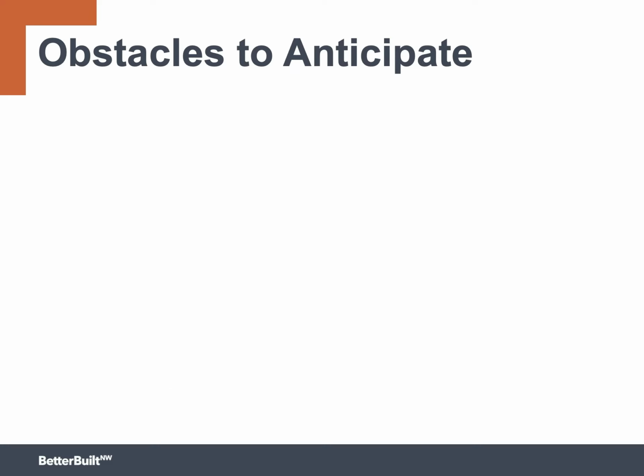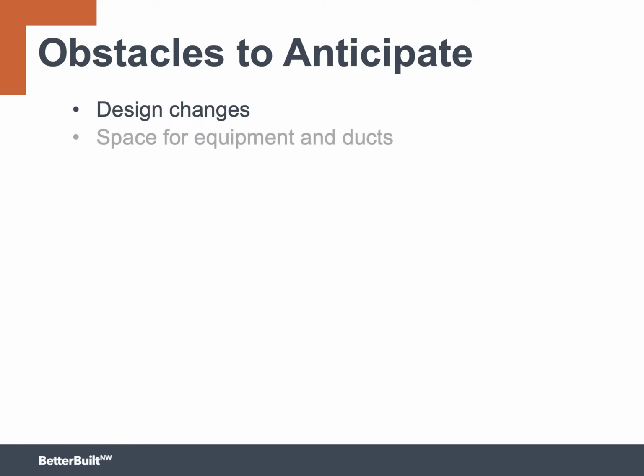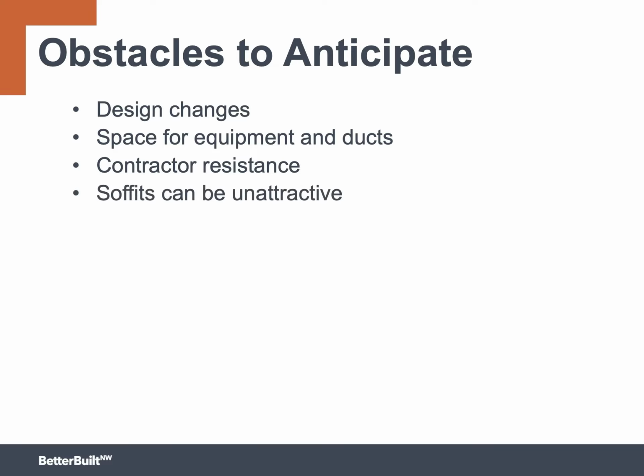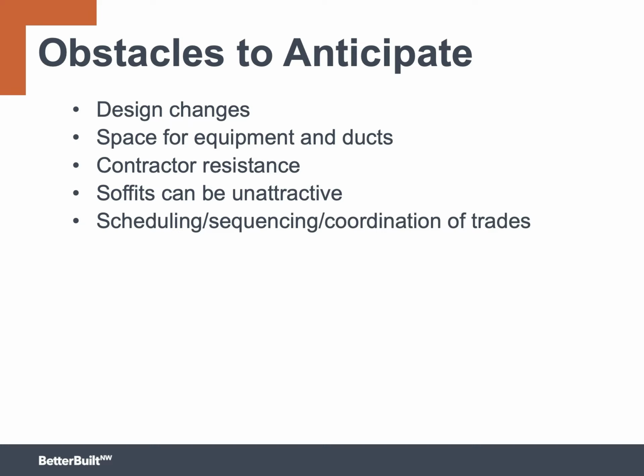There are some potential challenges to building with ducts inside too. You can have design changes such as the issue of extra height in the building. You can have challenges finding space for the equipment inside the conditioned envelope. You may find that the trades are resistant to this whole idea and you have to overcome some pushback. Some people may view soffits as unattractive. Sometimes scheduling or sequencing of the trades can be an issue. You might lose some interior space, or you may have secondary impacts or ripples through the floor plan.